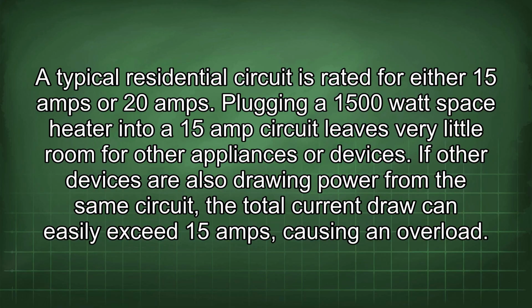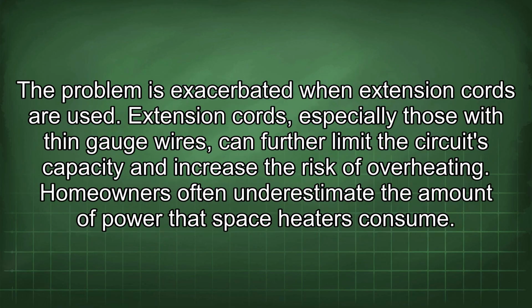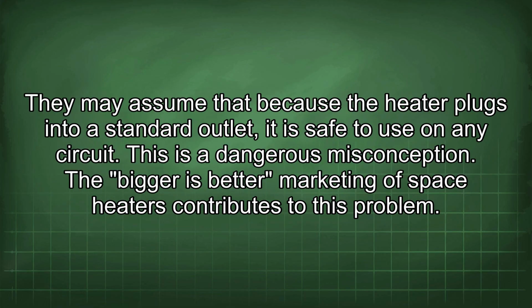If other devices are also drawing power from the same circuit, the total current draw can easily exceed 15 amps, causing an overload. The problem is exacerbated when extension cords are used. Extension cords, especially those with thin gauge wires, can further limit the circuit's capacity and increase the risk of overheating. Homeowners often underestimate the amount of power that space heaters consume. They may assume that because the heater plugs into a standard outlet, it is safe to use on any circuit. This is a dangerous misconception.